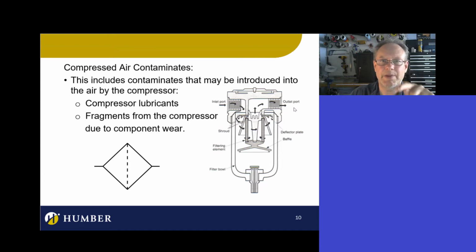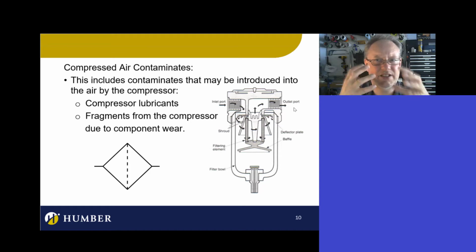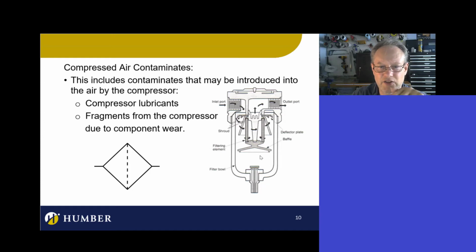Now, what happens is when the air is going through there, there's a dynamic in there. It's moving, right? The water vapor that's in there will get stuck on all of the surfaces. Water likes to stick to stuff. So it'll get stuck on all those surfaces, and this baffle here actually manages the water. It collects the water and it drops down the baffle and falls into the bottom here. And actually we have to drain this. So often these get full of water. Again, that depends on the environment you're in. So all of this filtration is very dependent on the environment you're in, what the atmosphere is like. Okay, good. So that's what's going on there.